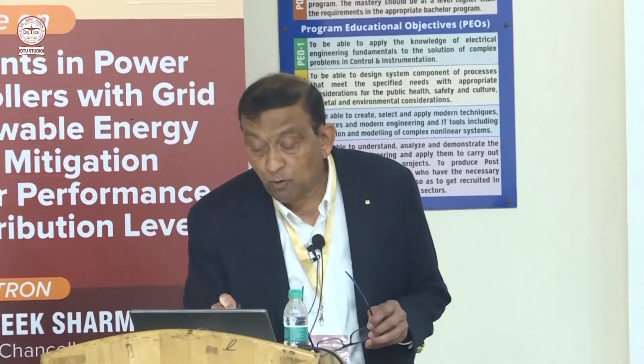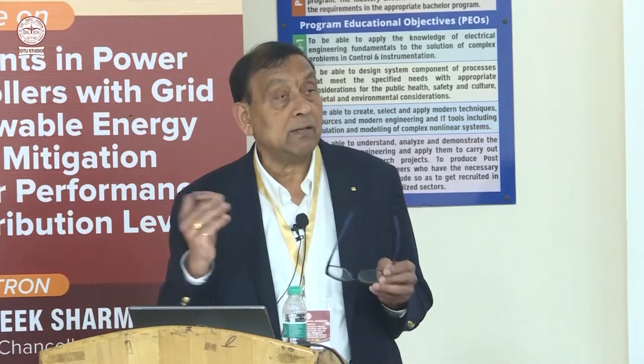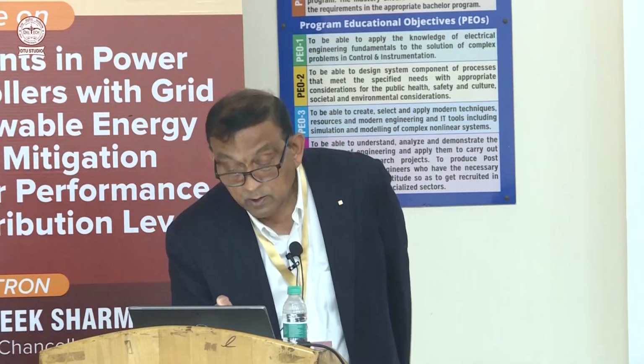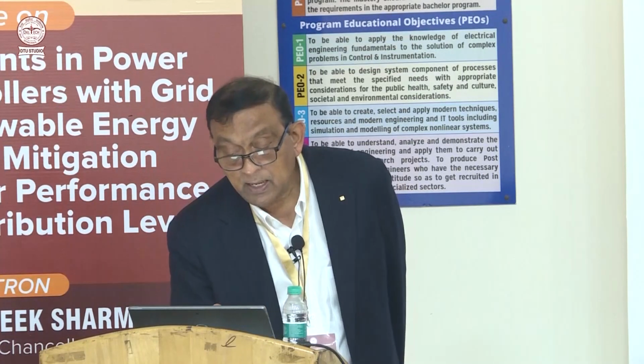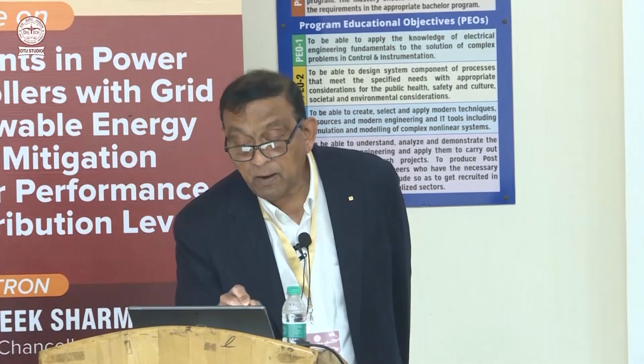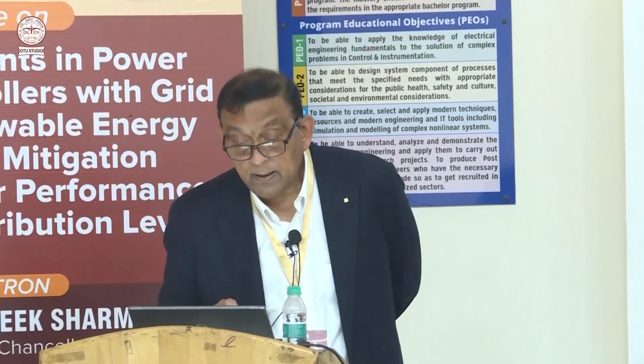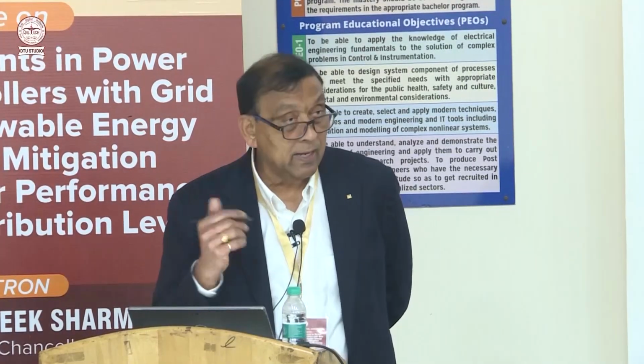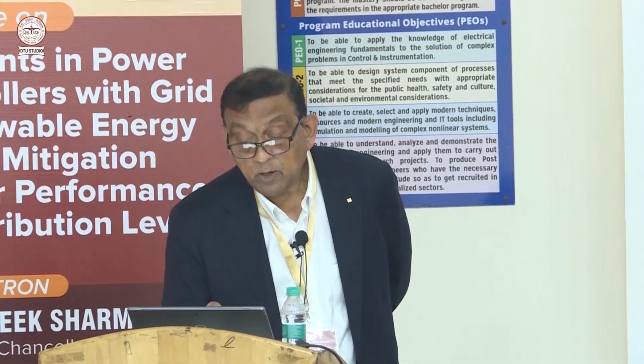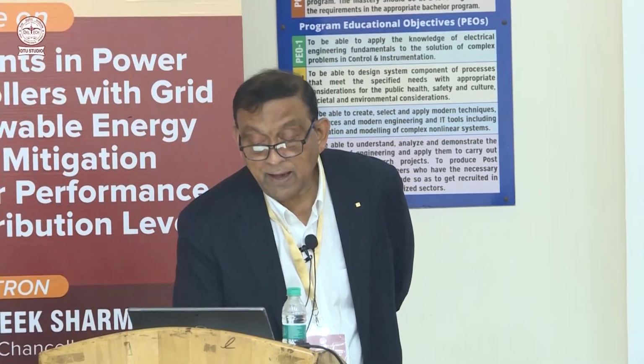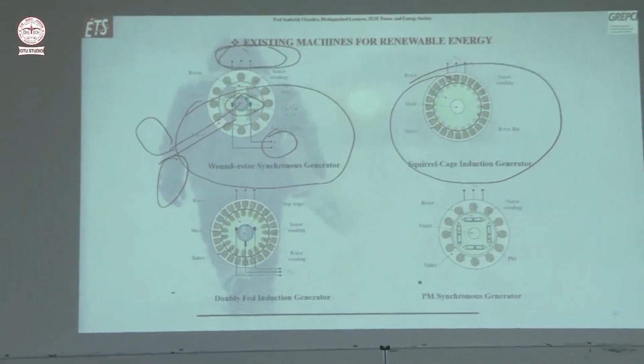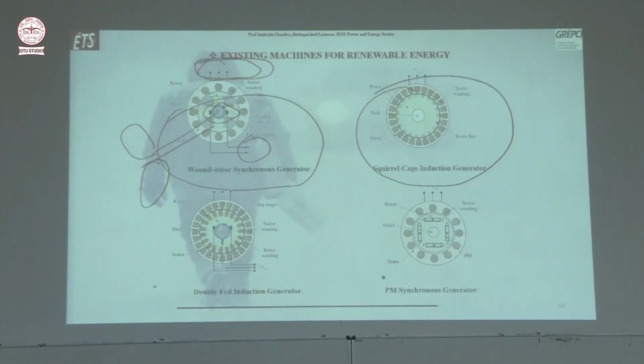Then there's the wound rotor synchronous generator, the classic machine. On the rotor side you have two slip rings and two brushes, and you can control active and reactive power at the terminals. But if it's connected directly to the wind turbine, the speed will be variable, so the voltage and frequency will also be variable. So you need full-size back-to-back converters to connect it to the grid.